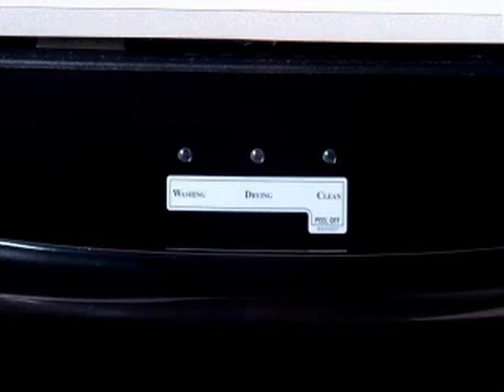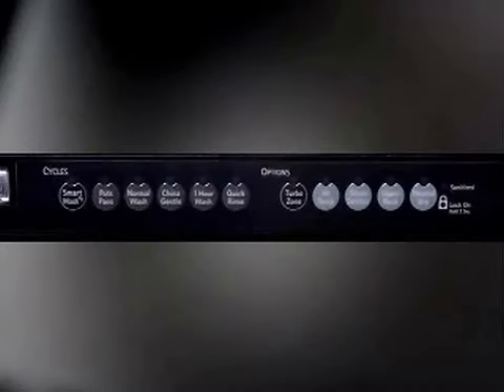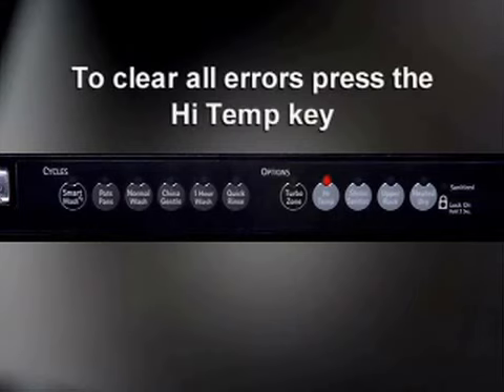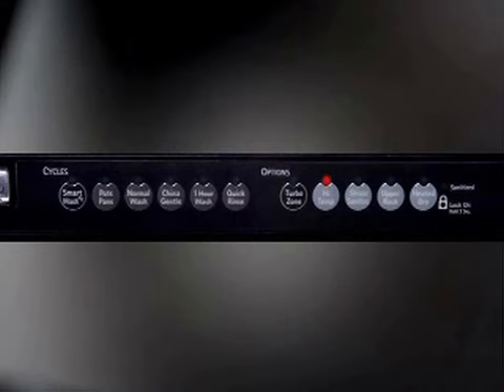The error code will repeat 3 times unless the start key is pressed to advance to the next error code. The control panel will remember the last 4 errors. After advancing past the 4th error, there will be a 10-second pause, then the high temp LED will light. To clear all errors, press the high temp key. The high temp LED will blink twice to indicate the errors have been cleared.